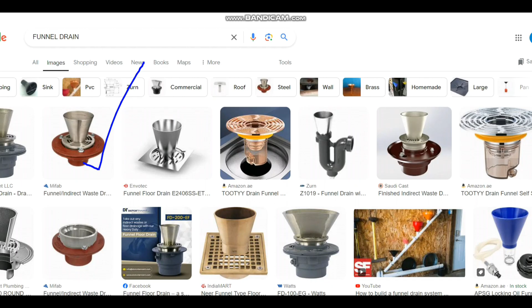For the funnel drain, for example, here the FCU or FAHU is located. The water will be collected like this and dropped like this, with an air gap maintained, not directly dumped into the drain. This is for the FAHU and AHU roof units. An air gap of about 2 to 3 inches minimum must be kept, and then the water is released from here through the funnel drain.